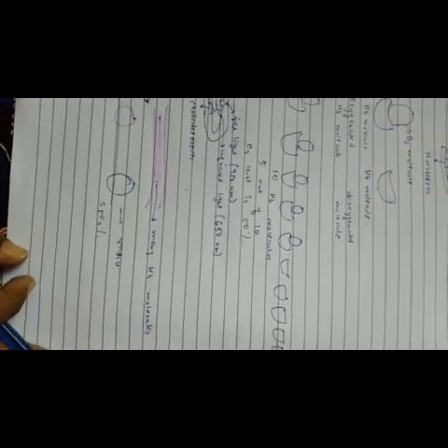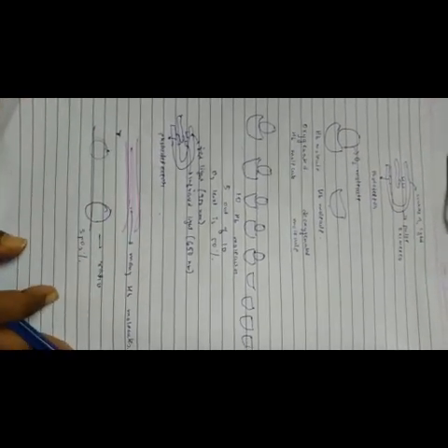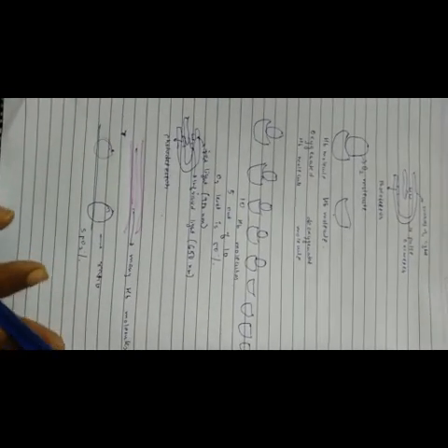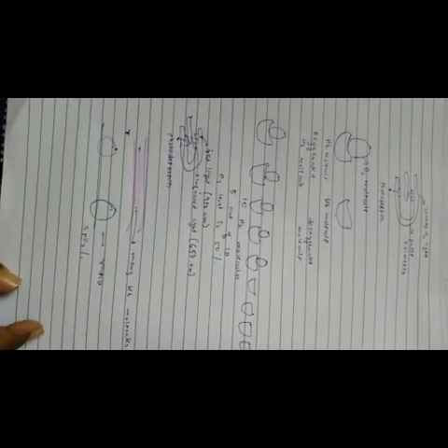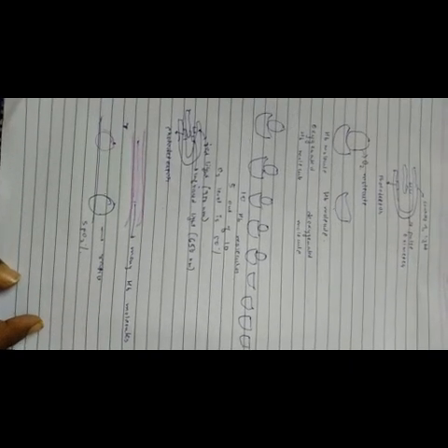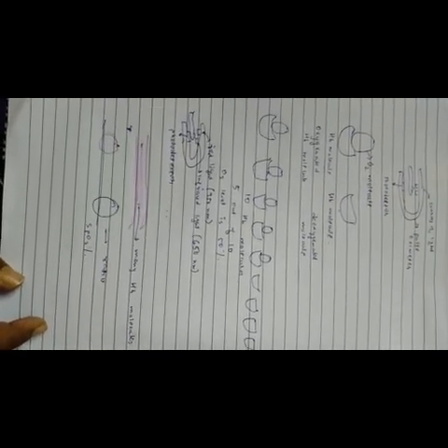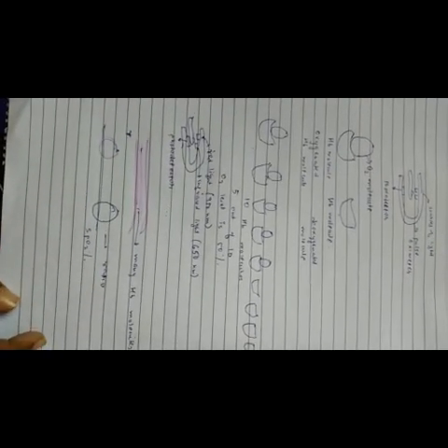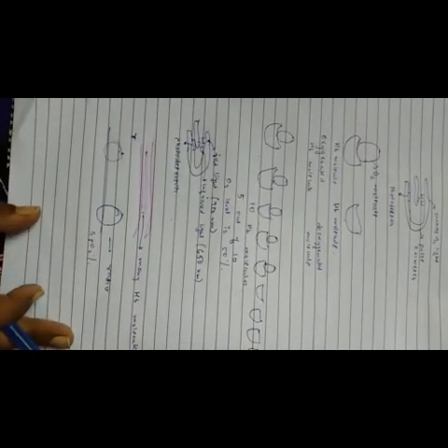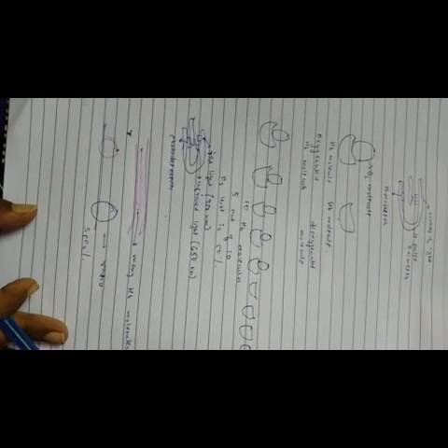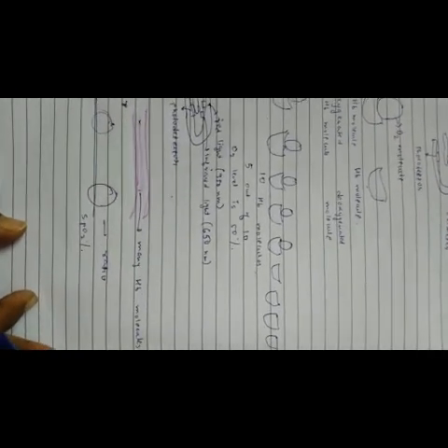But there's one complication: the size of the finger might be different for different kinds of people of different ages. So we have to calibrate the device so that we can normalize it for everyone, so that the blood oxygen level of all people gets monitored. There are many parameters according to which the device is calibrated. So I have told you till now how the SpO2 percentage is calculated, that the ratio is calculated, and all the machinery inside the pulse oximeter just calculates it.